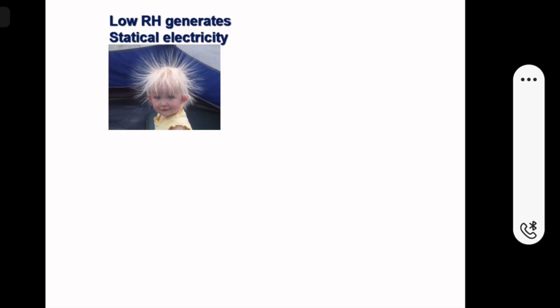And similarly, you also might have some experience of low RH situation. So in a low RH situation, static electricity is extremely bad for electrical things. Because nowadays we have printed circuit boards and very compact ICs, integrated circuits, where two conductors are placed very closely. So if RH is low, there is a chance that there will be sparking. There will be static electricity generation and sparking between two closely spaced conductors. And because of that sparking, it may cause short circuit.